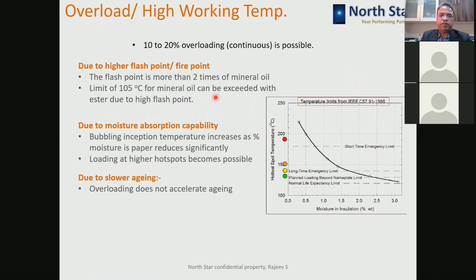So when you use esters in your transformer, you can overload, continuously overload. I am saying you don't have to balance between the phases of overload and underload, so that the duty cycle of 24 hours, if it is there, is respected. You can overload continuously around 10 to 20% of your rated rating because of these three properties: flash point, moisture absorption capability, and slower aging rate.